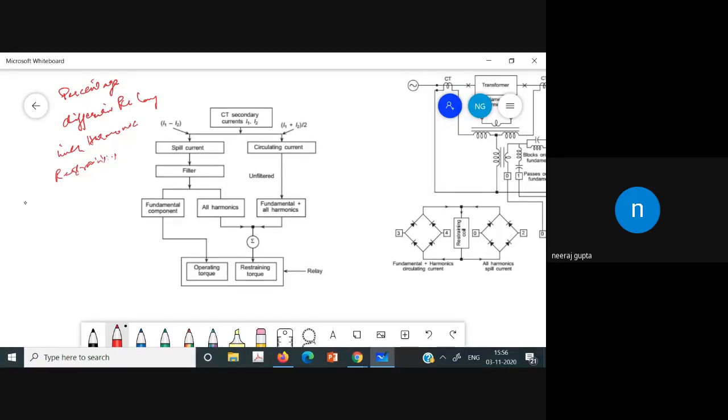However, this is not desirable, since the probability of insulation failure after the switching is quite high, and whenever we are desensitizing the relay, the insulation failure might occur at that particular point of time. So desensitizing the relay is not a practical alternative.